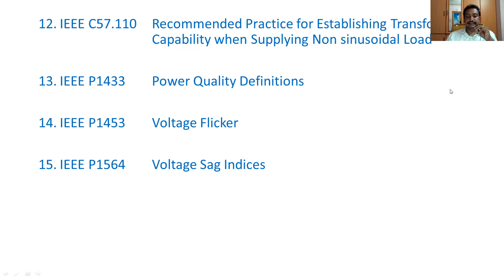IEEE 241, recommended practice for electric power systems in commercial buildings. IEEE 602, recommended practice for electric systems in healthcare facilities. IEEE 902, guide for maintenance, operation and safety of industrial and commercial power systems. IEEE C57.110 is the recommended practice for establishing transformer capability when supplying non-sinusoidal loads. So this is how to determine transformer capability for supplying non-linear, non-sinusoidal loads. Then the power quality definitions and terminologies. IEEE P1453 indicates voltage flicker. IEEE P1564 indicates voltage sag indices.